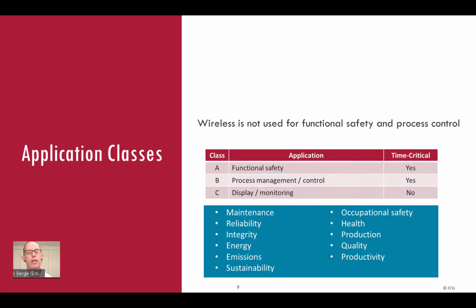Wireless sensor update period is usually set to 1 minute or longer to conserve battery life. This is too long for functional safety or process control. Therefore, we will not be talking about wireless sensors for functional safety or process control. Wireless sensors are mostly used to automate data collection for reliability, sustainability, and productivity.